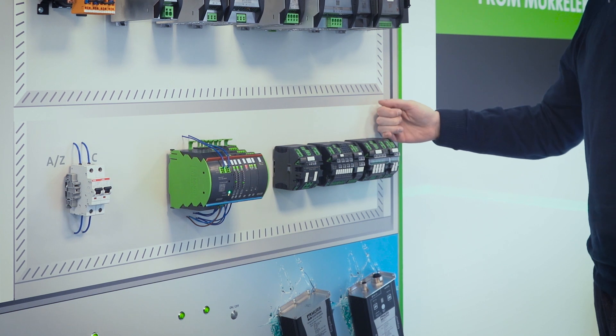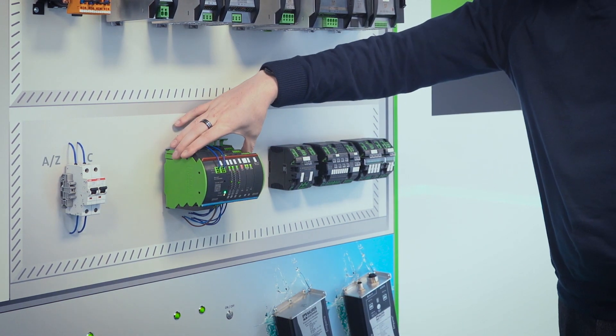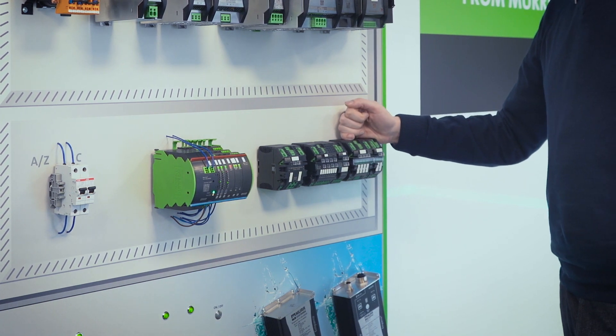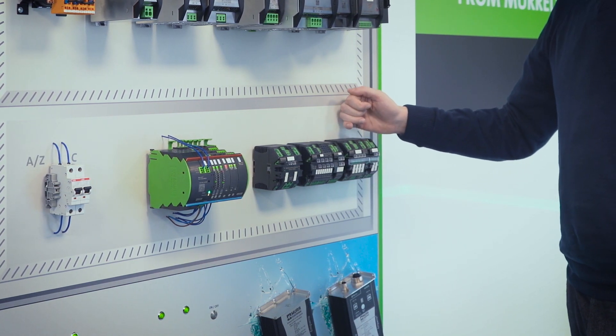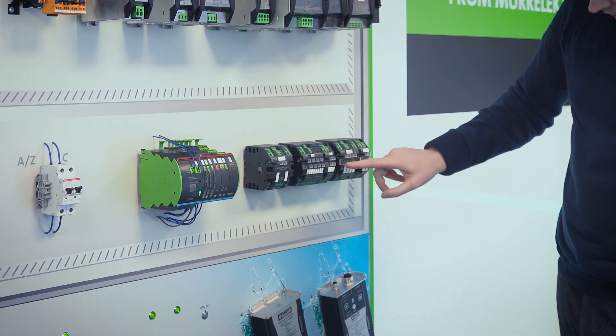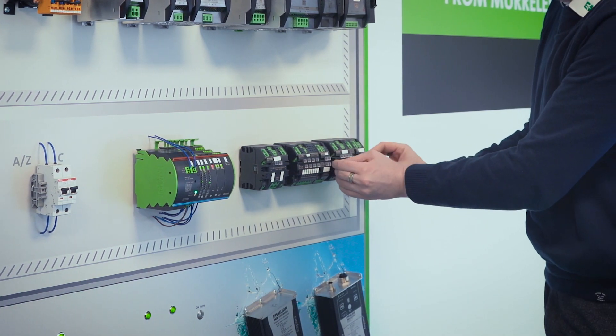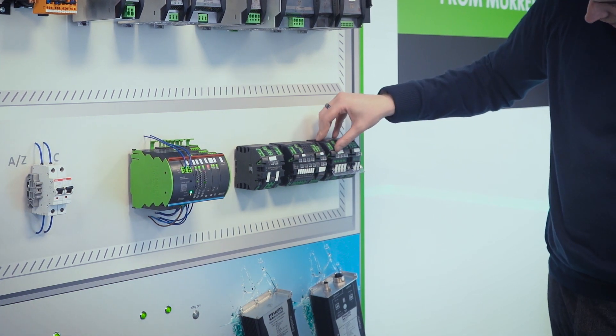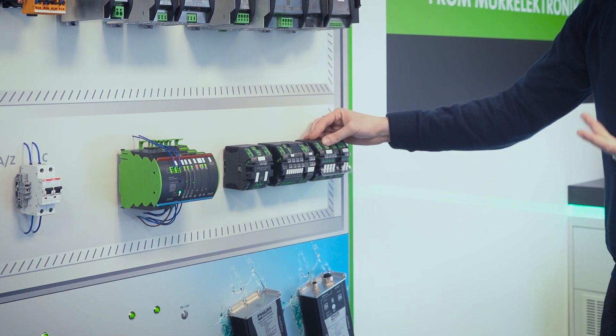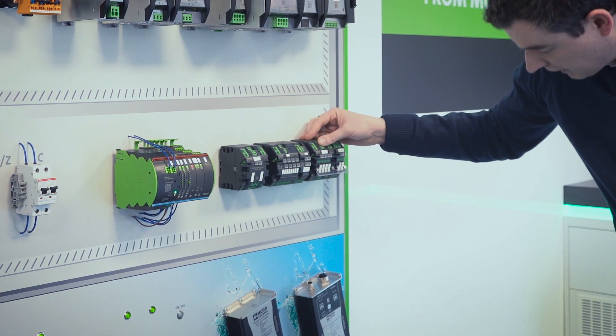There is also the MICO Plus, which has all the features and benefits of the Pro, including the 90% warning, remote control on and off, remote reset, and the alarm contact. These come with rotary switches, configurable between 1, 2, 3, or 4 amps; 2, 4, 6, or 8 amps; or 4, 6, 8, and 10 amps.